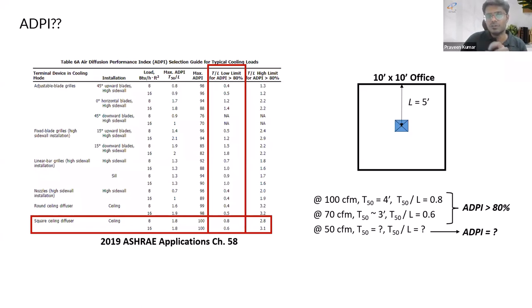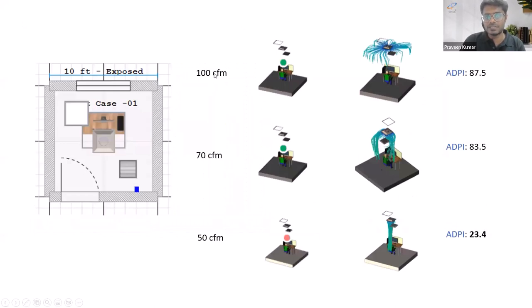So what we did was simulate this case study with three different CFMs in a single personal office space, 10 by 10 feet. We simulated it for 100, 70 and 50 CFM, and here is the ADPI, showing how CFM directly impacts the ADPI level, below 80, or well below 80 I'd say.